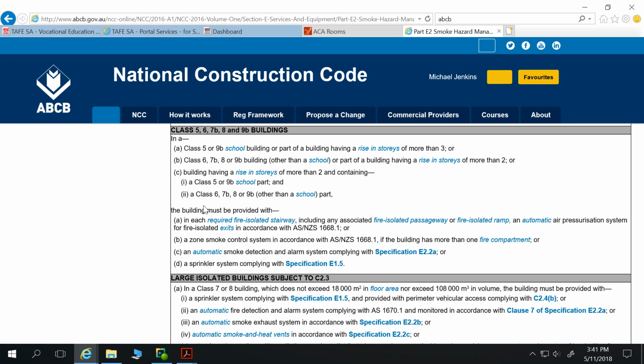Possibly an automatic smoke detection and alarm system complying with those specifications is a good idea, or a zone smoke control system in accordance with AS/NZS 1668.1 if the building has more than one fire compartment. Look, I'll leave that for you to choose. Basically, a zone smoke control system means that's ensuring that you don't get smoke shared between levels, between fire compartments. So that will be within your air conditioning system, baffles to ensure that smoke doesn't pass through, etc. in the event of a fire.